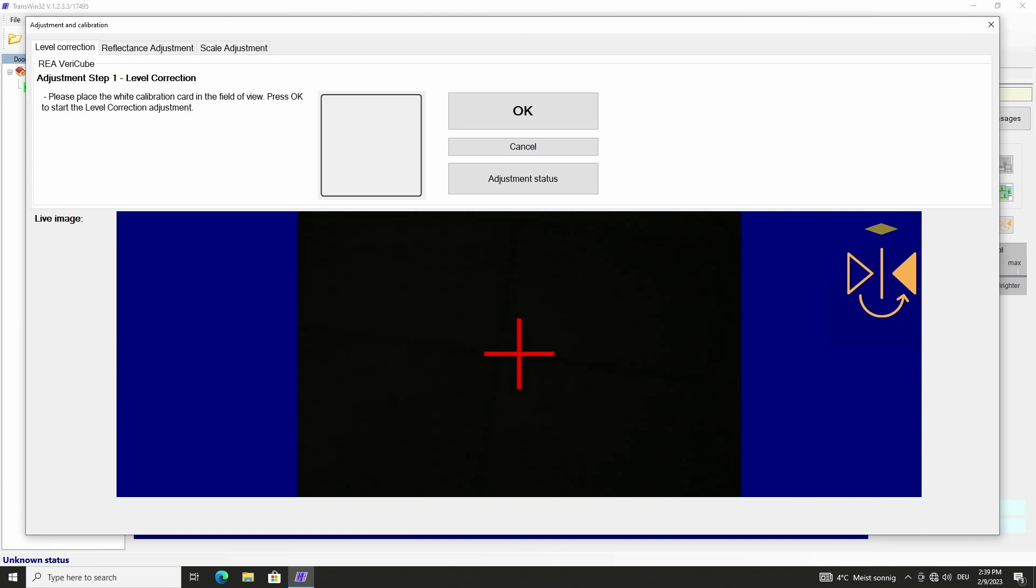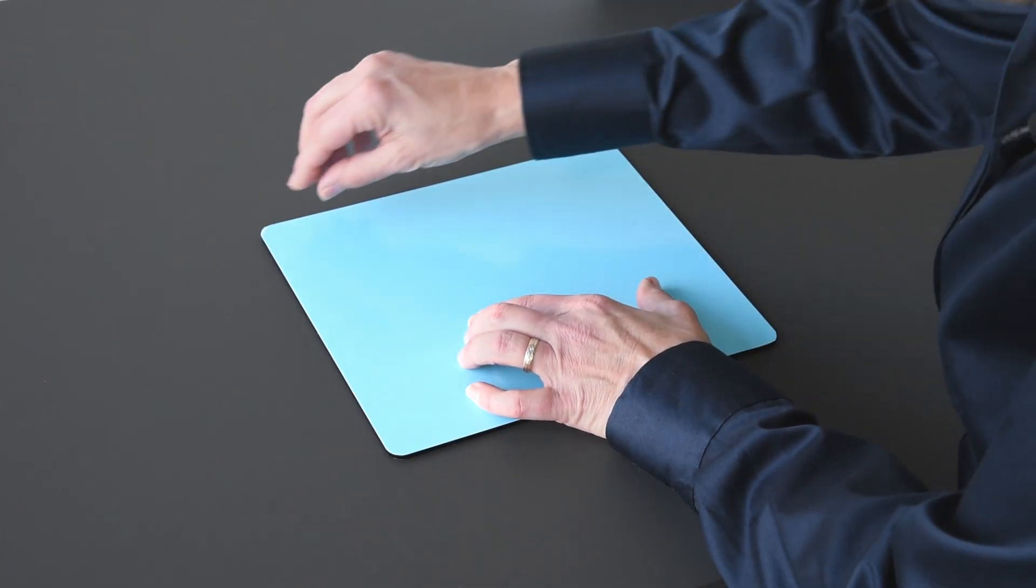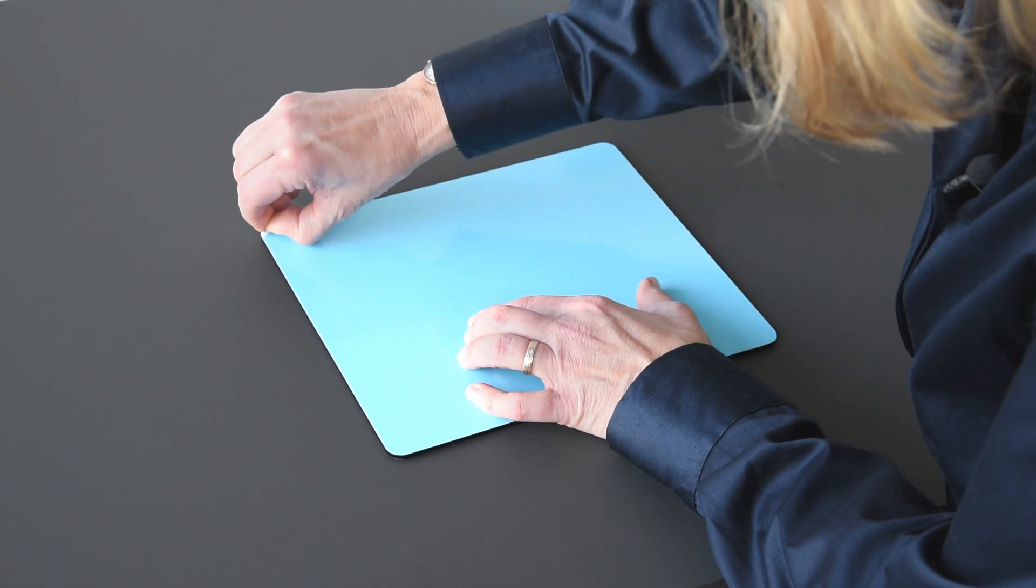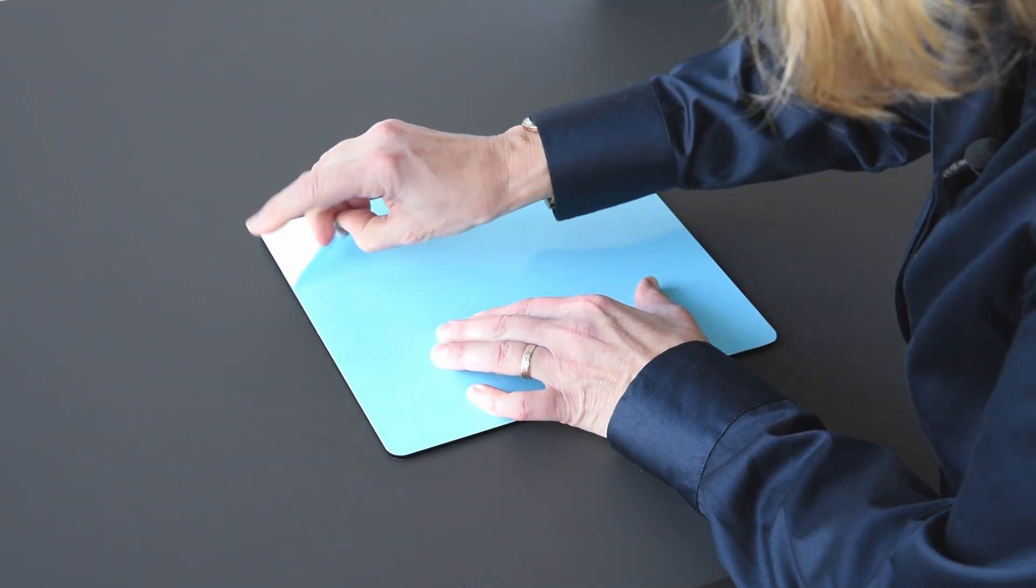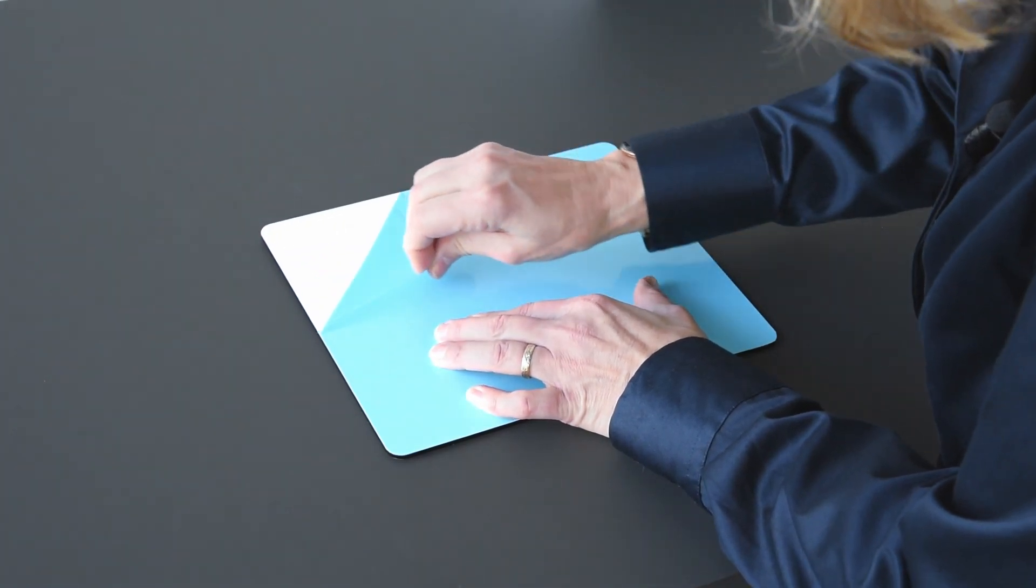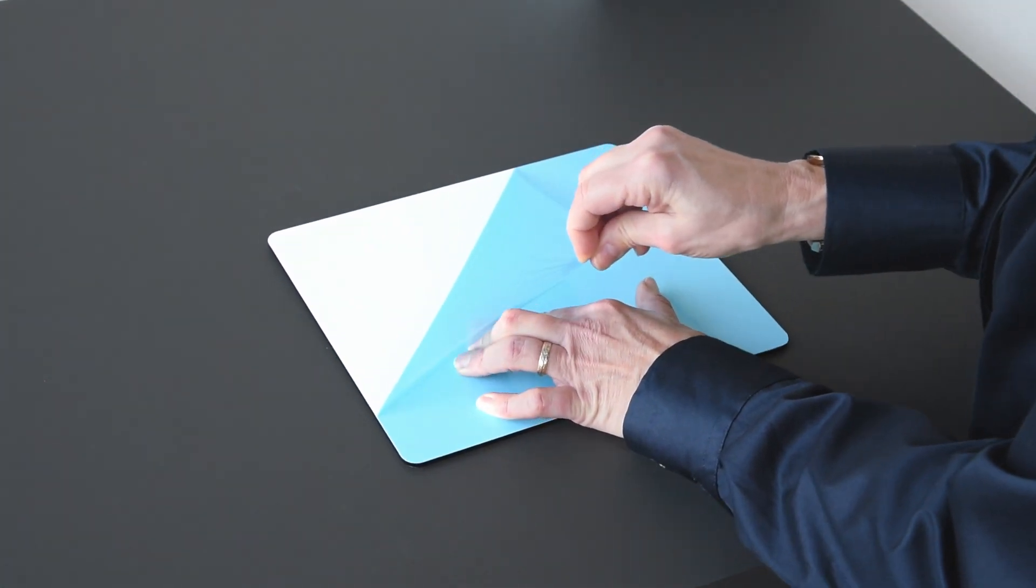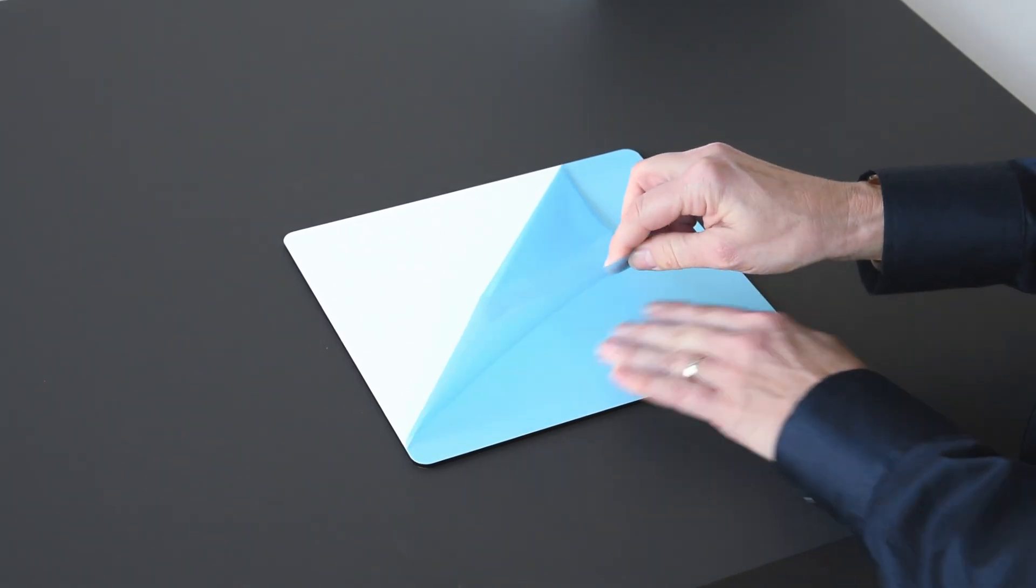The actual adjustment begins with the first step level correction. We take out the white card from the other folder and before first use we remove the blue protection foil.